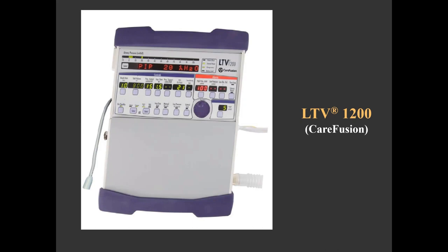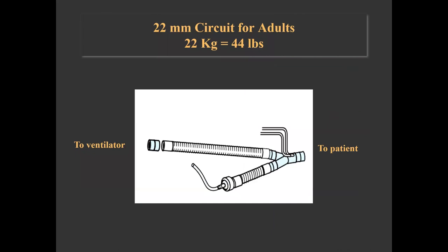I have no conflict of interest pertaining to the subject discussed. This ventilator is designed for invasive as well as non-invasive ventilation. The circuit has two limbs — inspiration and expiration — both connected to the patient Y-piece. A humidifier or filter can be added to the circuit.